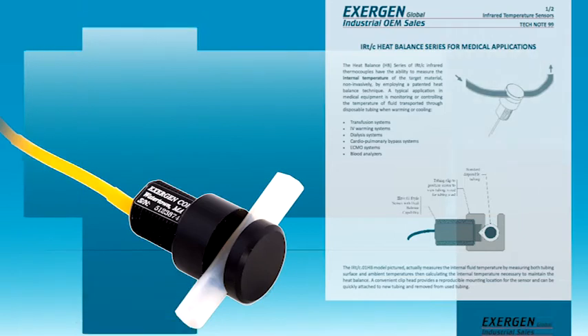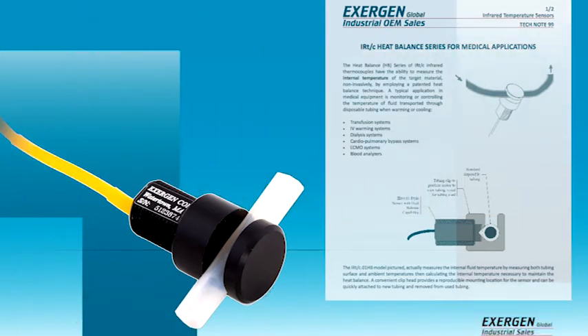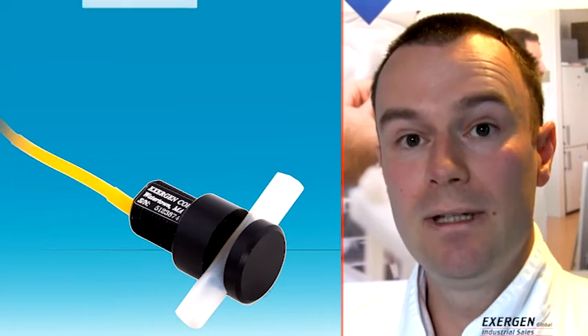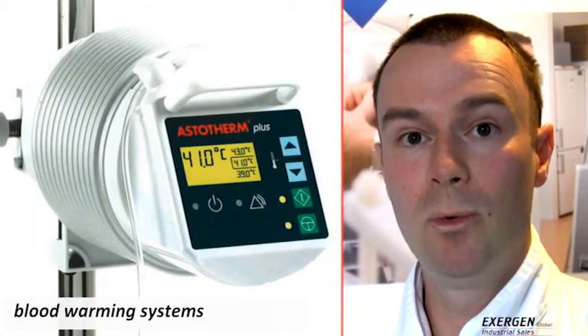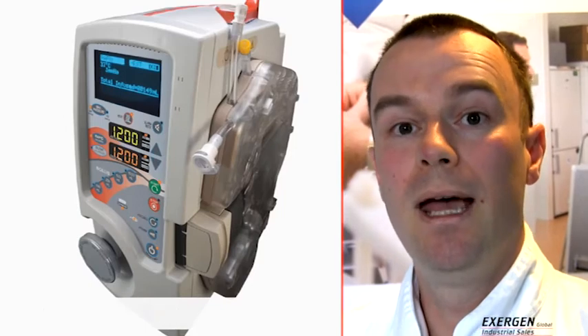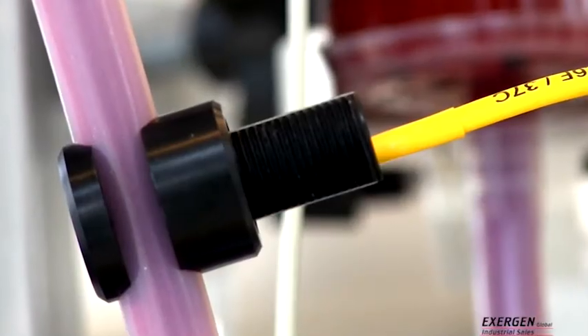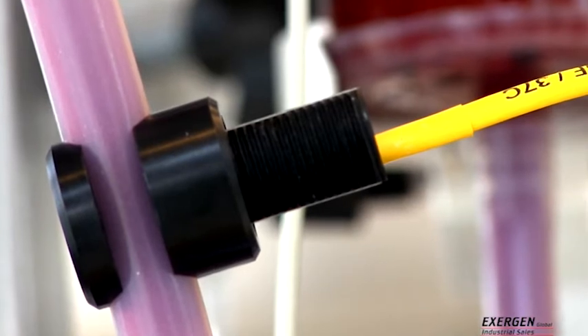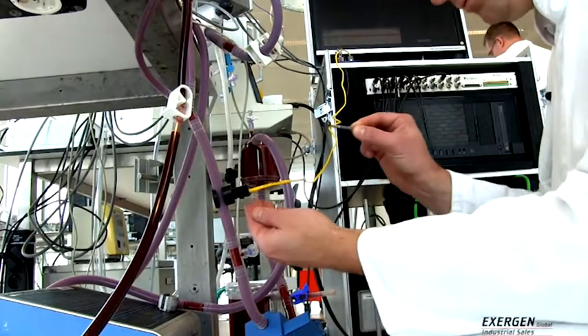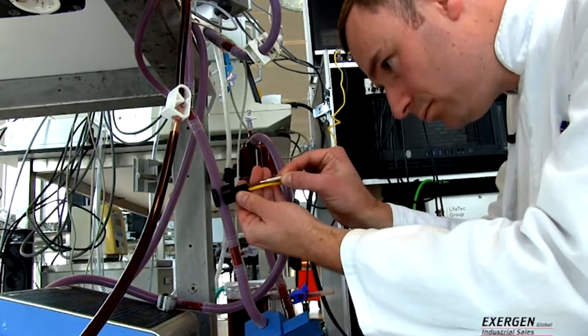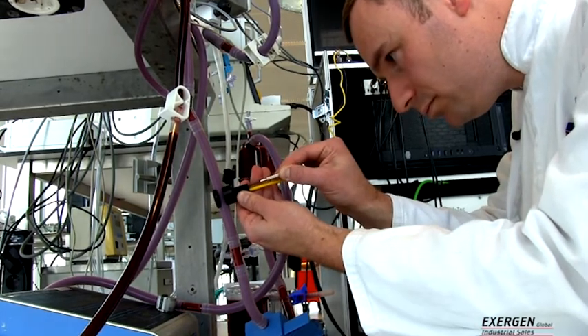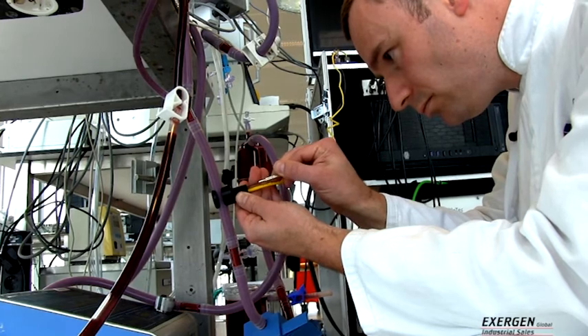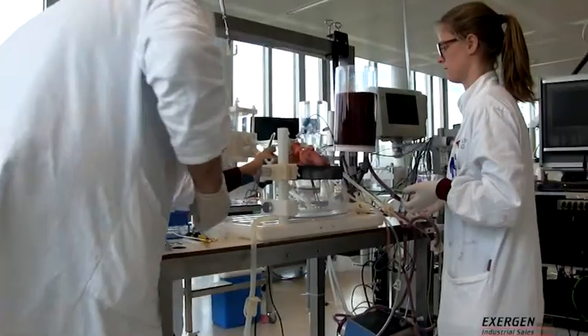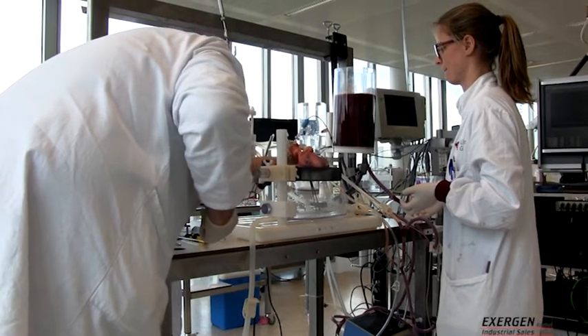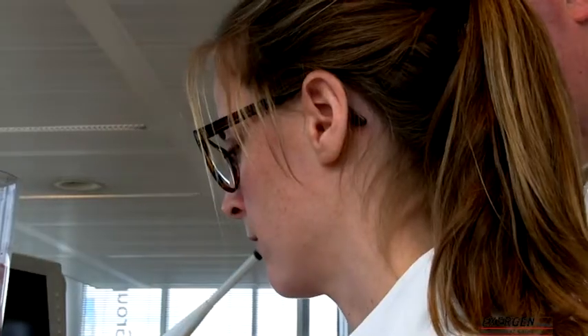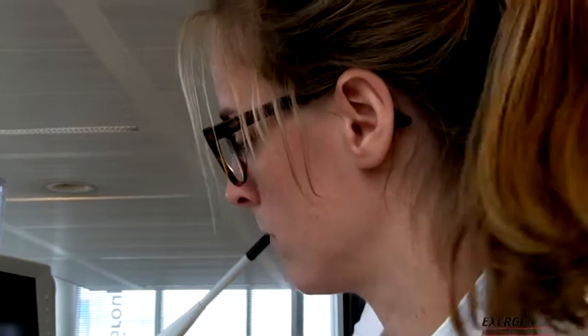Why is this method so important? It ensures accurate temperature measurements and sterility in medical devices such as blood warming systems, perfusion pumps and dialysis equipment. Exergen's heat balance sensor is the only sensor available on the market that can measure fluid temperatures non-invasively with a very high accuracy, ensuring patient safety and sterility. It speaks for itself that medical applications such as these demand sterile measurement solutions in order to avoid any contamination.